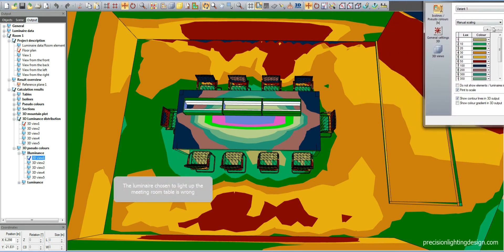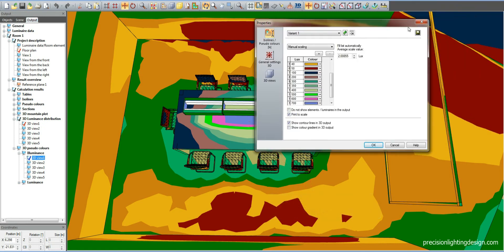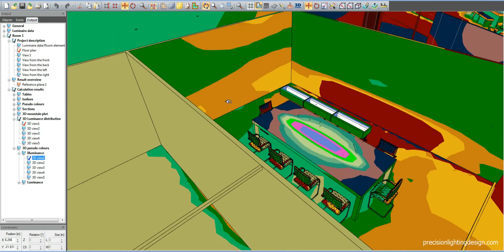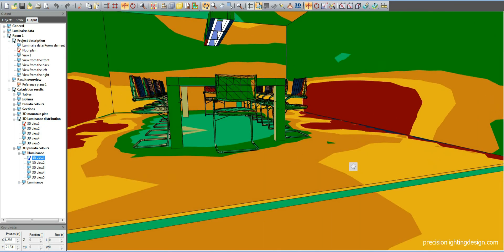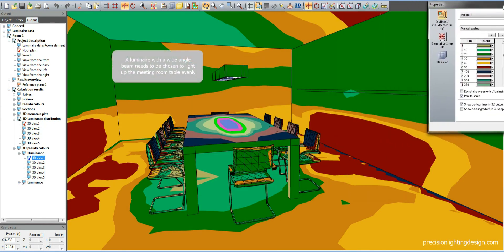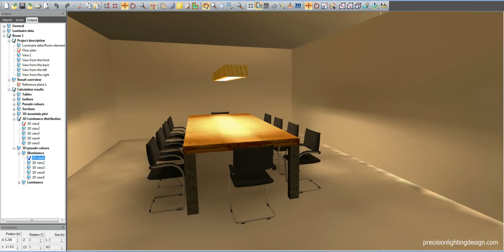In this meeting room, the luminaires chosen to light up the table are wrong. The center of the table is 700 lux, and the corners and sides of the table are between 100 to 200 lux. This means that the center of the table is too bright and the sides are too dim. A luminaire with a wide-angle beam needs to be chosen to light up the meeting room table evenly. Otherwise, the lighting will negatively affect the working conditions and result in discomfort.